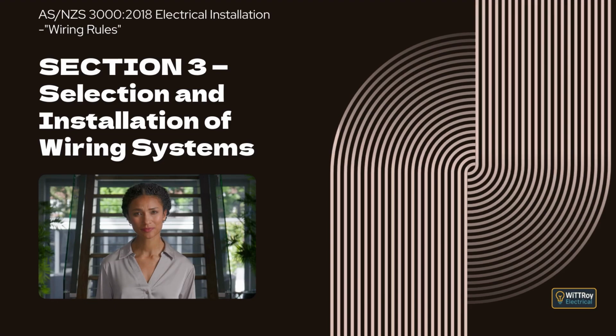Clause 3.12.2 Arrangements. This clause explains that aerial conductors must be arranged so they are safely installed and supported. It also introduces that further requirements apply to insulation, size, spacing, supports, and hardware, which are covered in the following clauses. Clause 3.12.3 Clearances. This clause explains that aerial conductors for low-voltage systems must be installed so that clearances from the ground, buildings, and other structures are not less than the minimum values required. These clearances must be maintained in all directions, taking into account sag caused by heat and movement caused by wind.